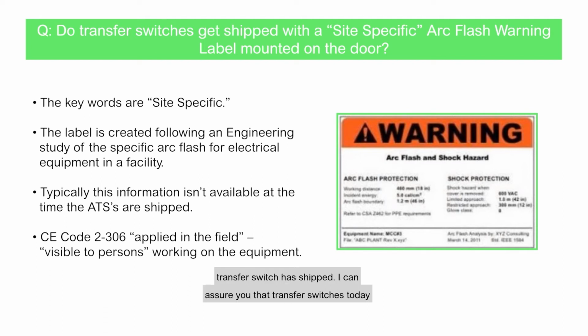So the arc flash warning label really needs to be applied in the field after the transfer switch has shipped. I can assure you that transfer switches today do get shipped with lots of warning labels on them, despite not having the arc flash warning label. This is because both UL and CSA standards require warning labels to warn people that the equipment contains two sources and there is a risk of shock and electrocution.